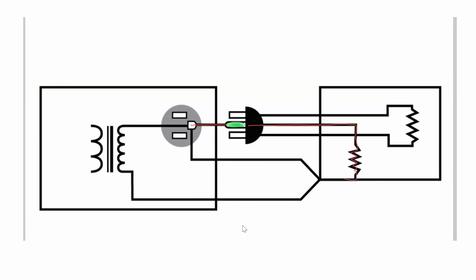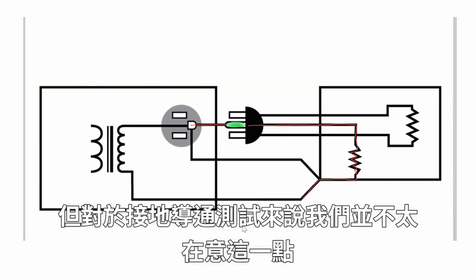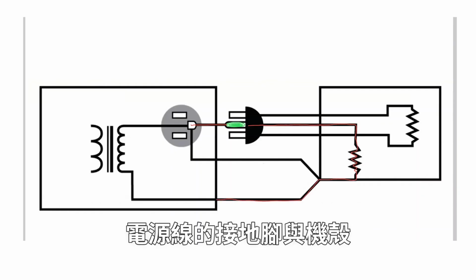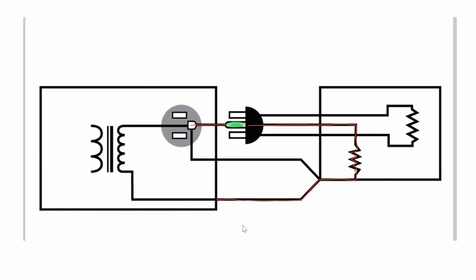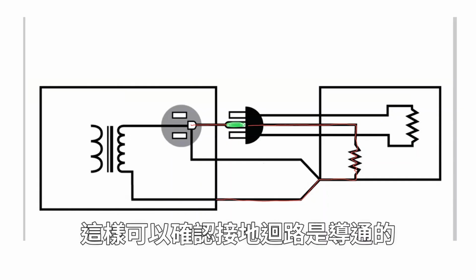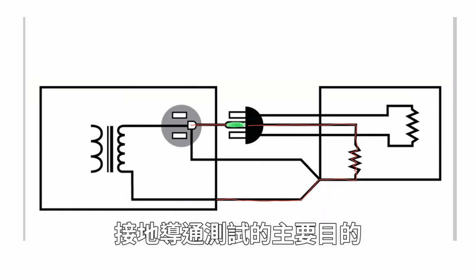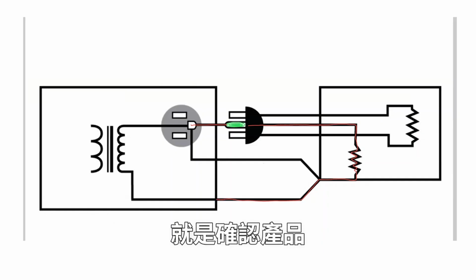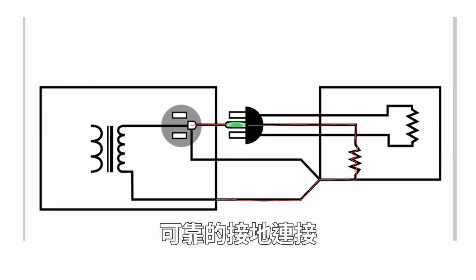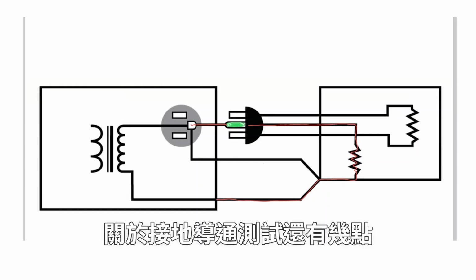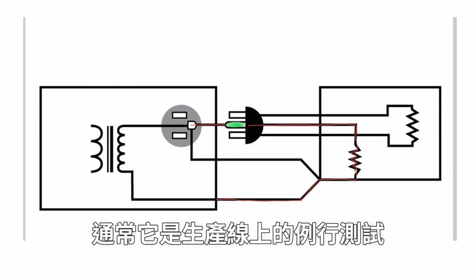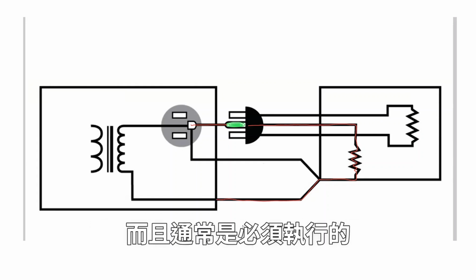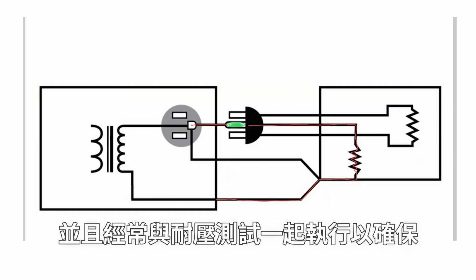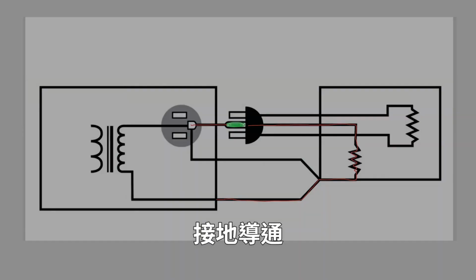It's going to experience some resistance, but we're not too concerned about that for the ground continuity test, because basically we're trying to measure continuity between the ground pin of the line cord and the chassis, which is going to verify that the ground circuit is continuous. That's what the ground continuity test is all about. A few other things to know about the ground continuity test are that it's usually required as a routine production line test and is often performed along with the high-pot test to ensure ground continuity.